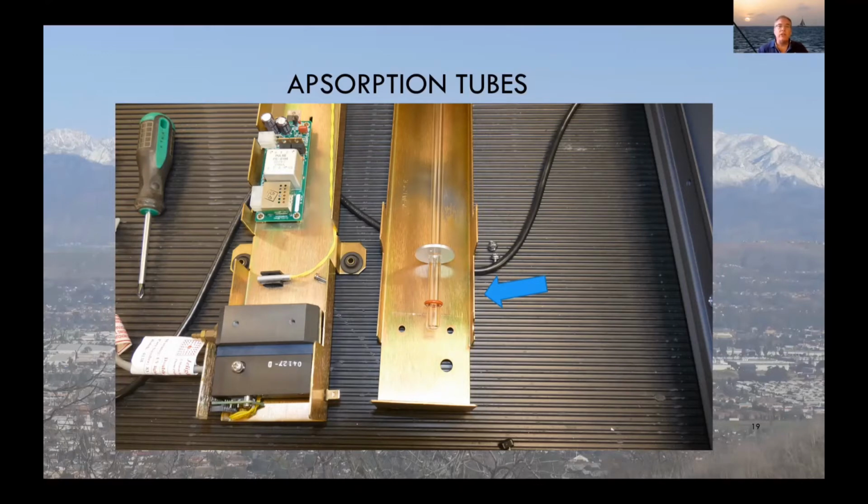After you have the absorption tube removed, a full cleaning is called for. Generally speaking, you can clean these just by rinsing with DI water, pushing a dust-free wipe or a Kimwipe through them, and drying them with pure air.